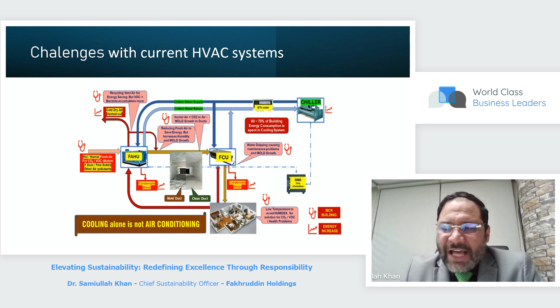So basically what we do is that we look at the internal carbon dioxide requirement and the air quality through sensors. We activate the FAHU based on the air quality of the building, based also on the ambient air quality. So we can also move into a predictive analysis, using the weather data, of when the ambient air quality will be good, and bring air into the building when it is required by the building.